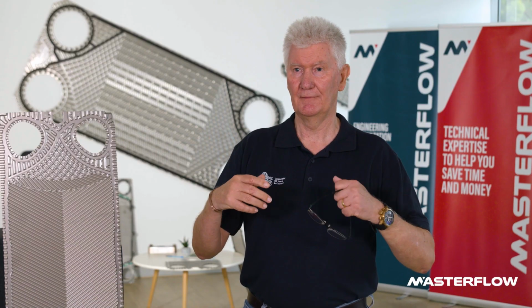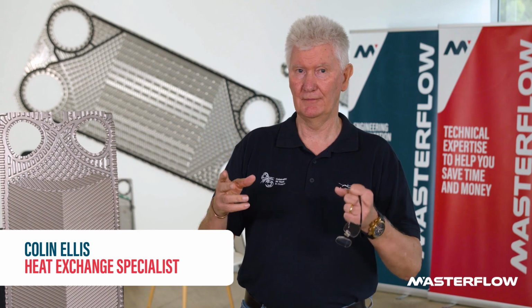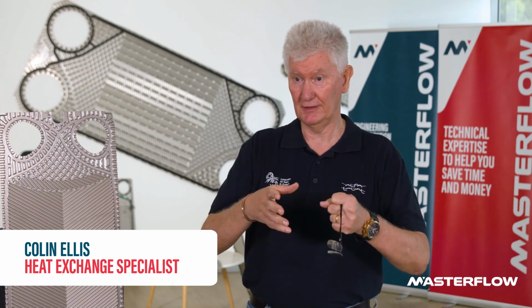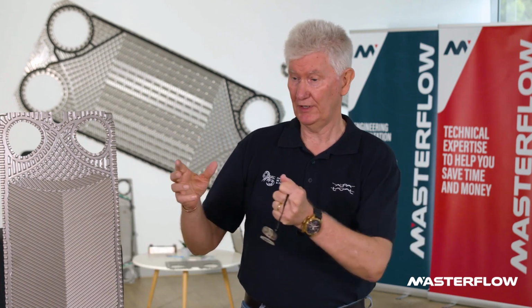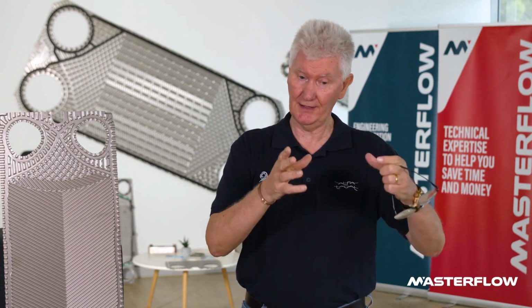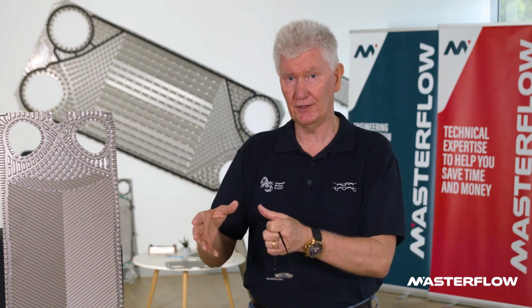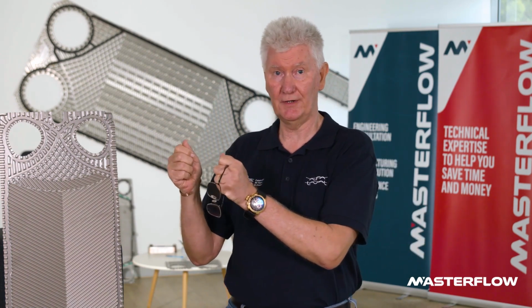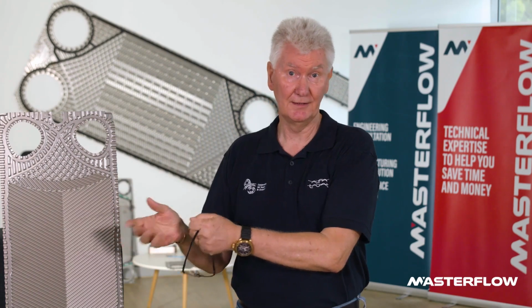Pressure drop for the heat exchangers is fairly nominal on how you design it. You can design for 100 kPa or you can design for 25 kPa. If you're running the heat exchanger at full capacity at 100 kPa and then halve the flow rate, you divide your pressure drop by 4, so 25 kPa. The problem comes in that if you design for 25 kPa for full flow and you halve the flow rate, now you've got 5 or 10 kPa pressure drop through the heat exchanger.